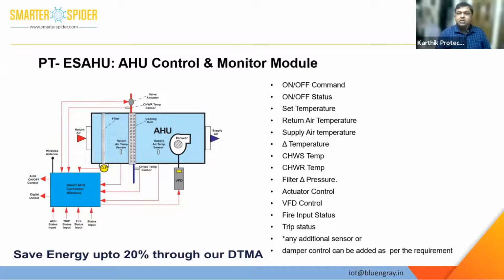Then we have 0 to 10 volt actuator control and feedback, and a 0 to 10 volt VFD control. We have a fire input status and trip status. Now to this we have a facility to add on sensors, for example, if you want to monitor the humidity levels inside the room, or the CO2 levels inside a particular area through the return air and all. We can add further modules to it, like damper controls and all. Now this is for a chill water based AHU.